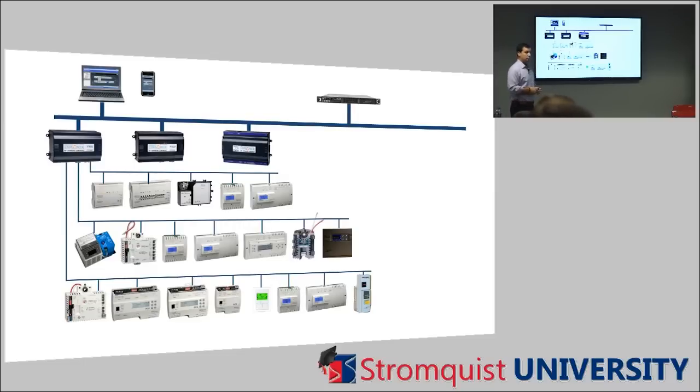Okay, so what's your solution on that? So then we would run a LAN trunk. We daisy chain all these LAN controllers in. Boom, we can just do one. We don't have to have multiple. We don't have to daisy chain if we don't want to, though obviously in every case you're going to. So we have our LAN trunk and we have our BACnet trunk. We pull them into the Jace.